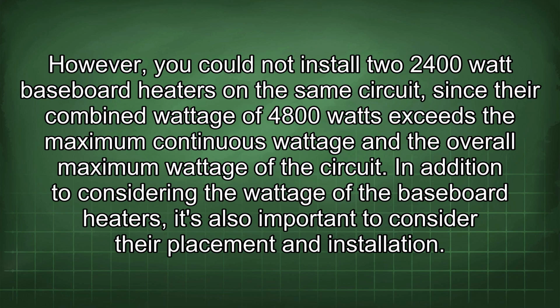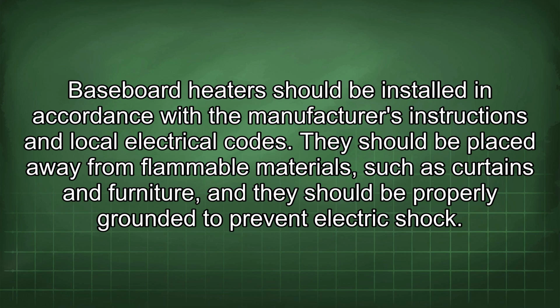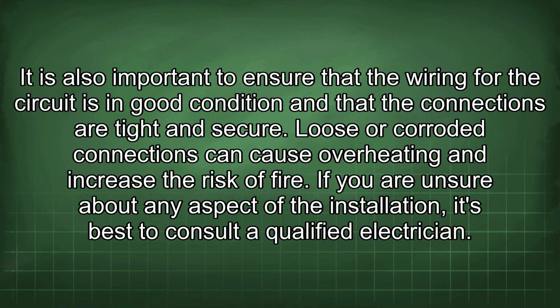In addition to considering the wattage of the baseboard heaters, it's also important to consider their placement and installation. Baseboard heaters should be installed in accordance with the manufacturer's instructions and local electrical codes. They should be placed away from flammable materials such as curtains and furniture, and they should be properly grounded to prevent electric shock. It is also important to ensure that the wiring for the circuit is in good condition and that the connections are tight and secure. Loose or corroded connections can cause overheating and increase the risk of fire. If you are unsure about any aspect of the installation, it's best to consult a qualified electrician.